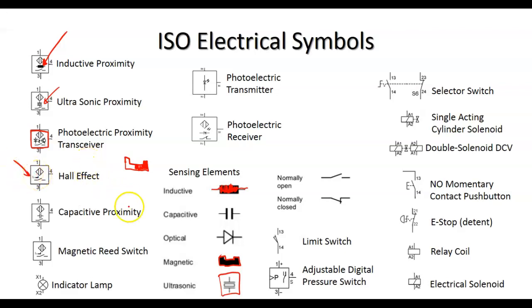Now notice, this has the same symbol, but it's a magnetic reed switch. A magnetic reed switch is a 2-wire sensor, while a Hall effect sensor is a 3-wire sensor. Can y'all see the difference? Notice this one has a wire 4, while this one only has a 1 and a 3, because wire 3 powers through the load.